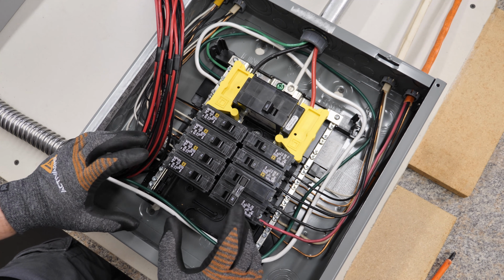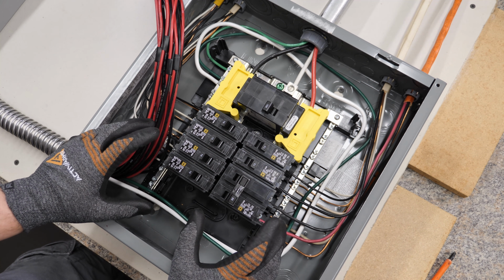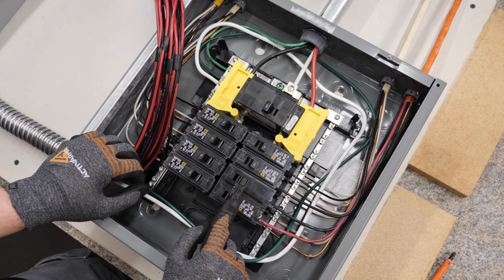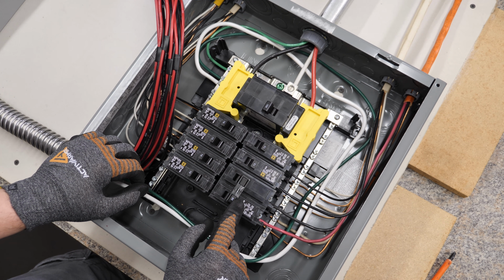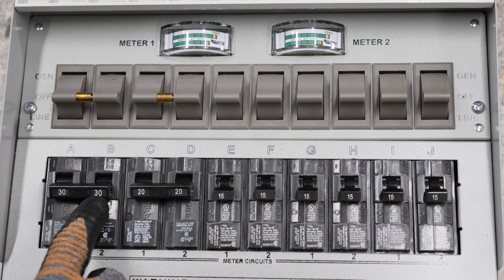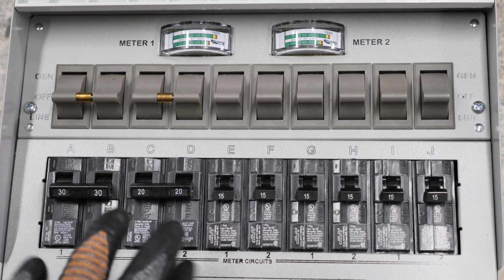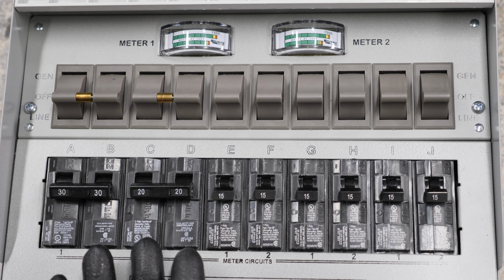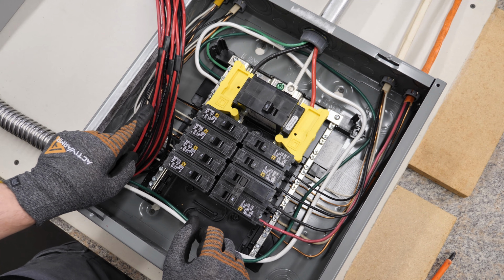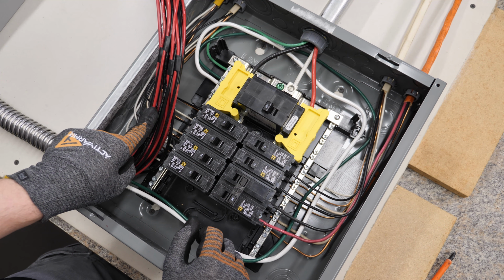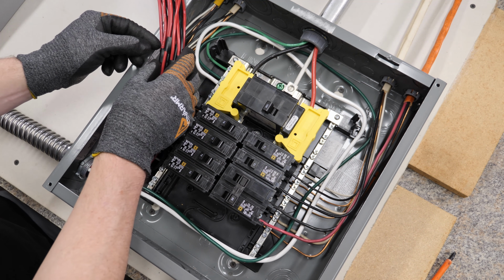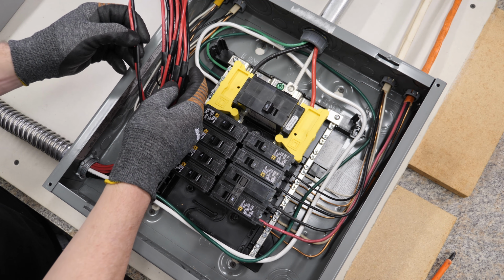Now we're going to act like we have a 240 volt well pump, wiring up this double pole 30 amp circuit breaker. On the transfer box, we'll be going off of spot A and B, since that's a 30 amp double pole circuit breaker as well. So we need to find A and B in the red and black wires, which are going to be the thickest wires available in here.